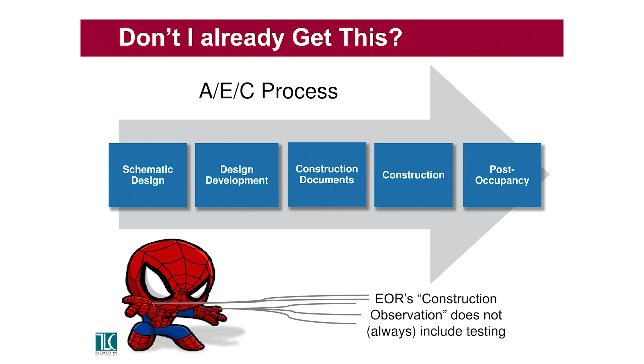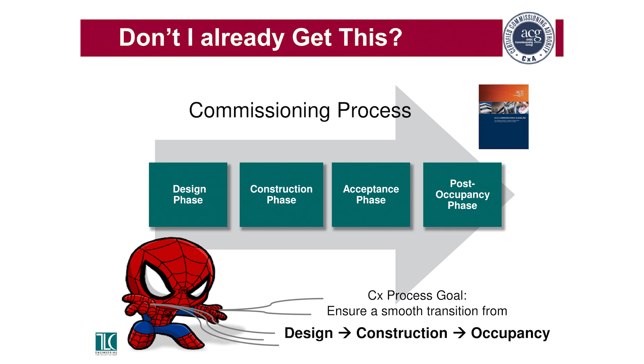Obviously, the traditional process unfortunately doesn't have the rigor in testing. The EOR's scope traditionally doesn't have the level of testing and documentation you'd want, certainly in a life safety situation like a hospital's emergency power systems. Sometimes it does, but sometimes it doesn't. And of course, our job as commissioning authorities is to help the project and the owner transition from design to construction to occupancy, and that's where we bring the value.